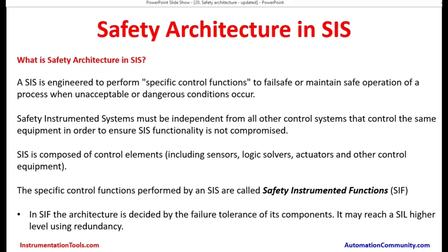They find out and tabulate different types of hazards that can happen across the plant in the process areas. For each scenario, for example, if it is a boiler, the fuel gas or fuel oil entering the boiler can get to high pressure and create a fire inside the boiler, or may get external to the furnace also. Likewise, it can go to low pressure or low flow — another scenario for the same equipment. A set of control valves and on-off valves in a particular gas line or pipeline may function to provide protection against any hazard. This is why it is called a safety instrumented system.